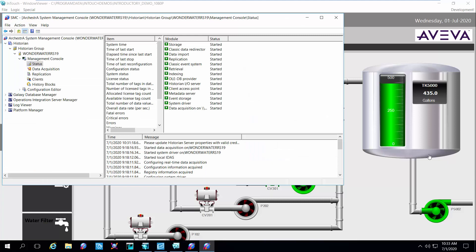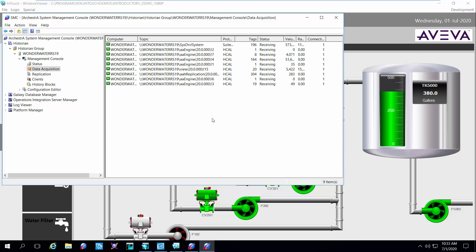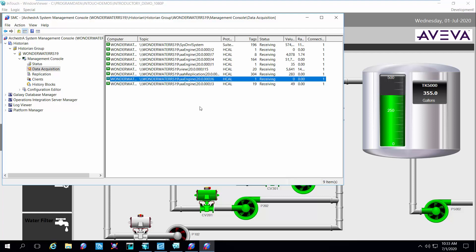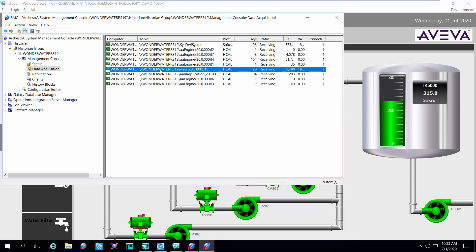So let's take a look behind the scenes at what's happening at the historian. You can see I have the system management console open, looking at the status of the historian, and everything is up and running. If I click on the data acquisition tab, you can see these are the data sources that are pumping data to the historian. I have some engines here — this is information coming from a system platform Galaxy running on this node. But if you look at the view application, this is where the InTouch application we just configured is pushing the data over to this historian. You can see it's receiving 20 tags.